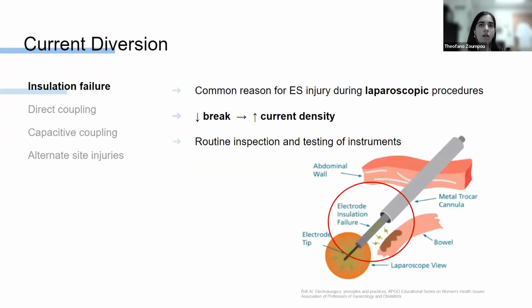First, we have insulation failure. This is a common cause of electrosurgical injury, especially during laparoscopic procedures. Just to remind you, Kinga just talked about that. Current density is inversely proportional to the surface area. And that means the smaller a break is, the higher the current density will be at that point. And we run the risk of injury to nearby structures, like the bowel, for example, in the sketch. The newer devices are usually disposable, and also they have monitoring systems that can detect stray energy leaks. However, we should always be vigilant, and we should always very carefully inspect and test our instruments before use. Keep in mind that breaks can sometimes be very small, and thus they can very easily go unnoticed.